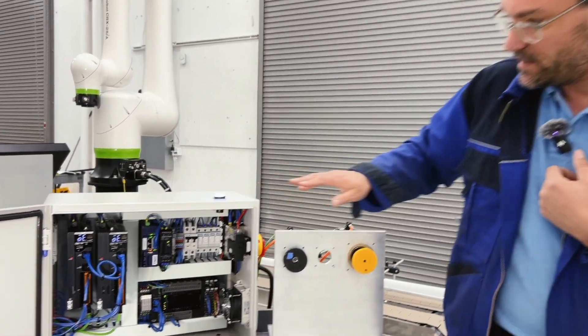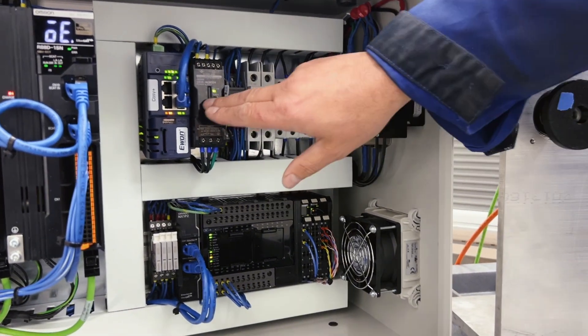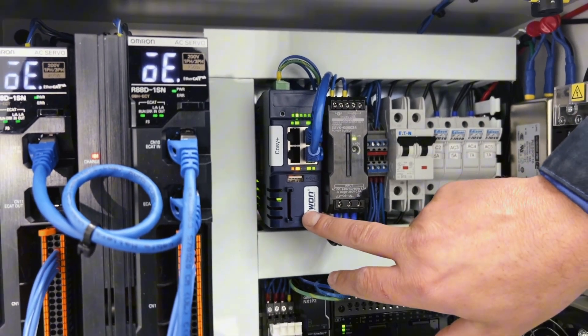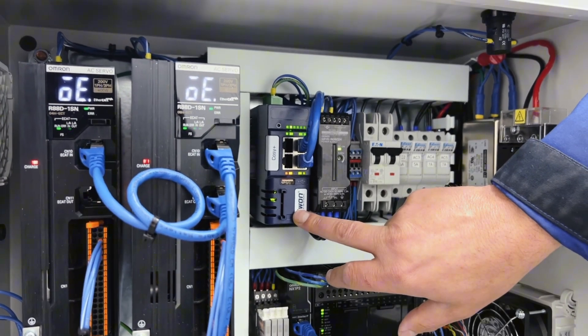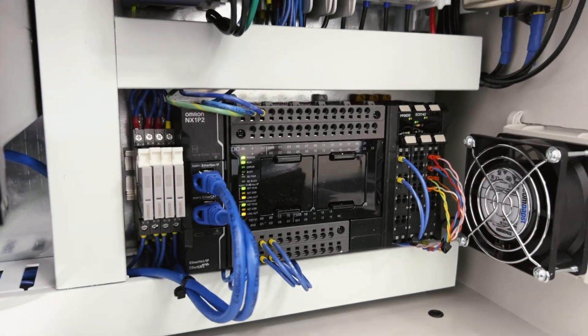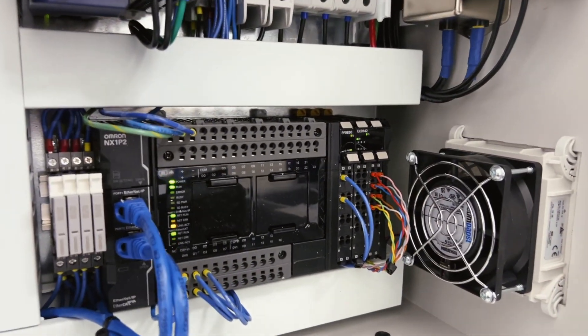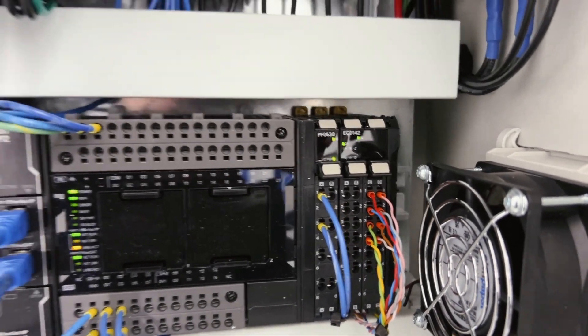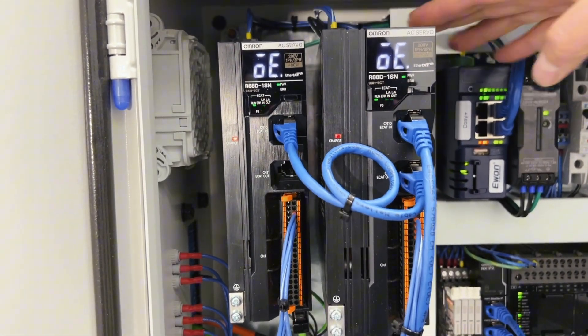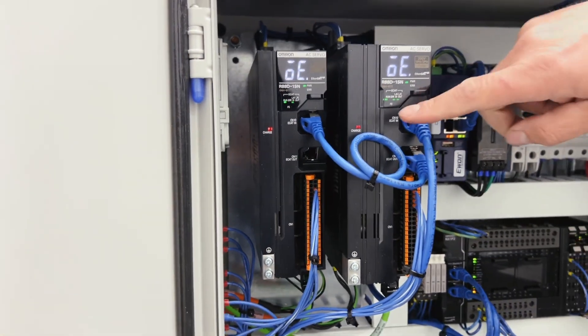The system consists of — and Ashley will zoom in now — a standard controls enclosure with regular power distribution and a DC power supply. All our systems are equipped with an eWON Cosy for remote support, so we can remotely service the system, download new software, or help troubleshoot. We have an NX1P2 Omron PLC and motion controller with EtherCAT, a feedback module, and a high-speed counter for the external encoder. At the heart of the system are our dual-axis servo drives: a 400-watt Omron servo drive and a 750-watt Omron servo drive connected via EtherCAT to the PLC.